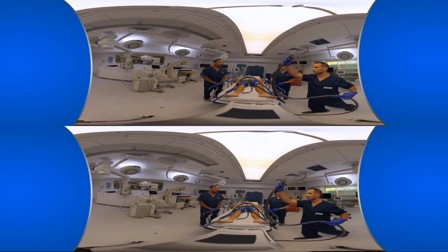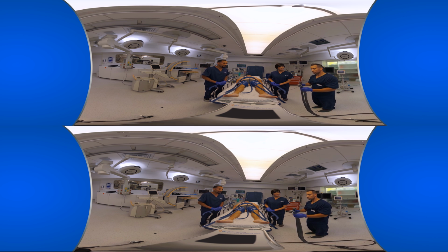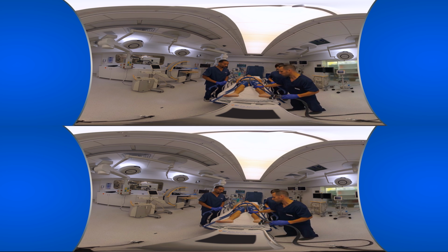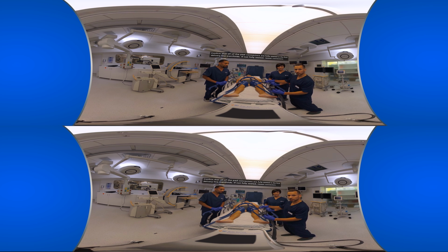In order to make our connections, we want to start by holding the tubing of the fluid delivery line and also the tubing of the patient's gel pad. We'll simply insert the clear connector, making sure we avoid grabbing onto it, and listen for that audible click.